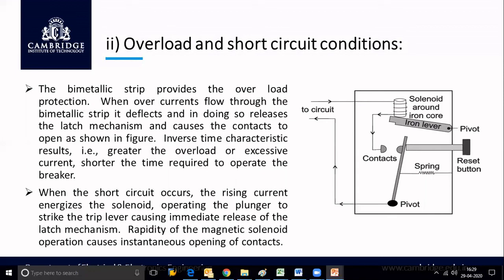Inverse time characteristics means that the greater the overload or excessive current, the shorter the time required to operate the breaker. If the increase in current is more, then the operating time of the breaker will be very small. Next, when a short circuit occurs, the rising current energizes the solenoid, operating the plunger to strike the trip lever, causing immediate release of the latch mechanism. The rapid operation of the magnetic solenoid causes instantaneous opening of the contacts.